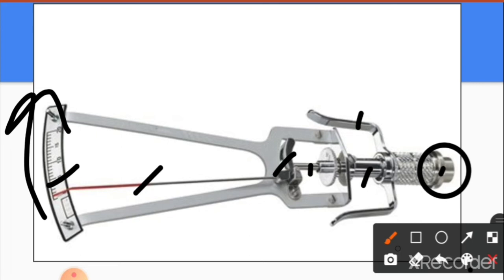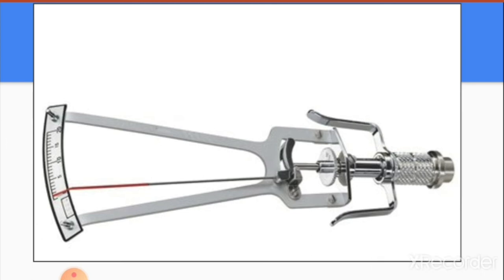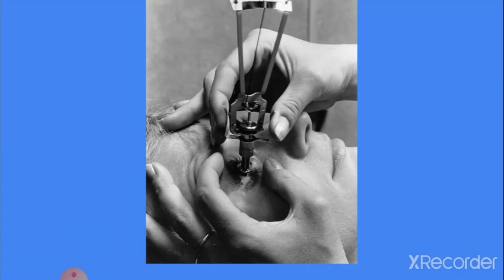For example, if you place 5.5 g on the Schiotz tonometer and the needle does not cross the four-scale mark, you change the weight to 7.5 g. If with 7.5 g the needle crosses the four marking on the scale, you then convert that reading in relation to that weight using the chart provided with the tonometer. This is how IOP is measured with the Schiotz tonometer.